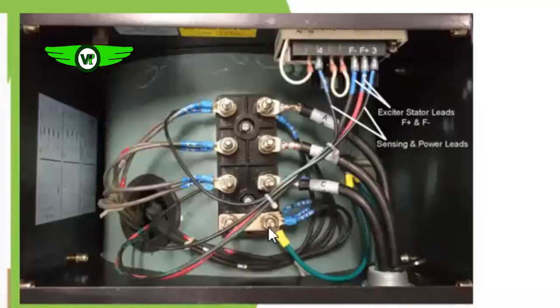Okay, so now this is the start point, as we said. This is the midpoint of the windings, which means that whatever you have here, you have half of it on this part. So if we are having 415 phase to phase here, we are supposed to have 220, or 200 phase to phase here. Then neutral, from neutral, if you place your black probe on the neutral, while you are on the AC voltage selection on your digital multimeter.